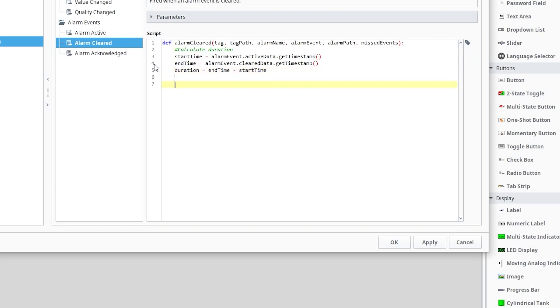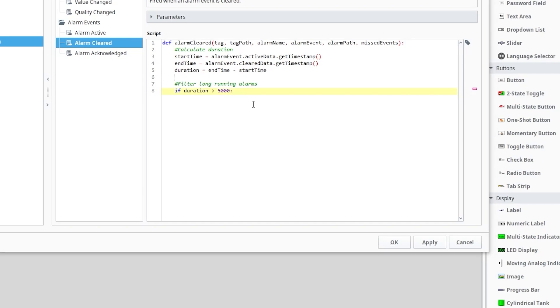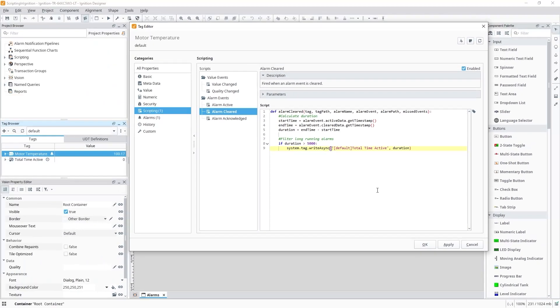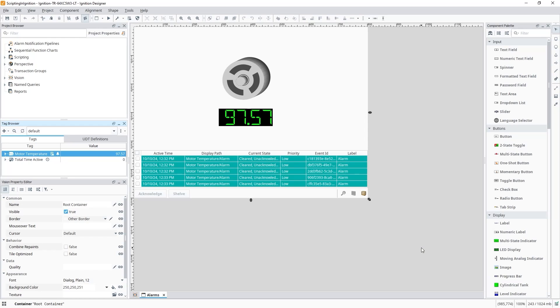Finally, we'll add an if condition here to evaluate when the alarm was active for a significant amount of time. We'll say when the alarm was active for more than 5 seconds, I'll write the value of our duration to the totalTimeActiveTag, which already has tag history set up. With our scripts in place, let's click on OK.